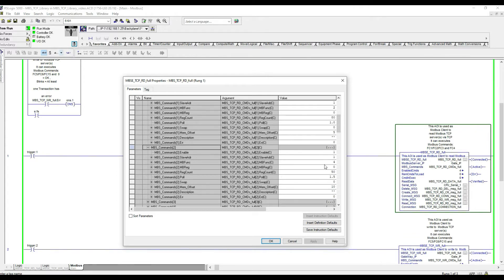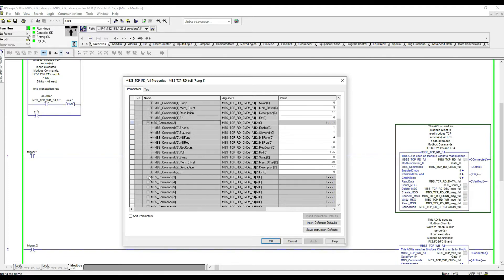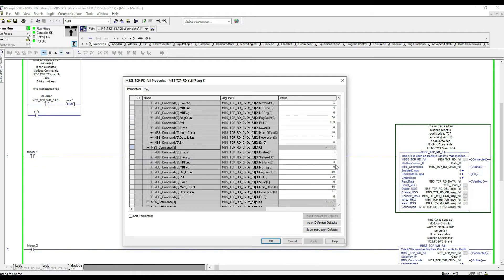Command number 4 reads the 50 input registers configured in Modbus, storing the result starting from element 10 in the read array. The last command reads the holding registers using function 3, reading 50 registers. Because we read 50 starting at element 10, the next command starts from element 60 for the next 50 registers, so we avoid overlapping data.